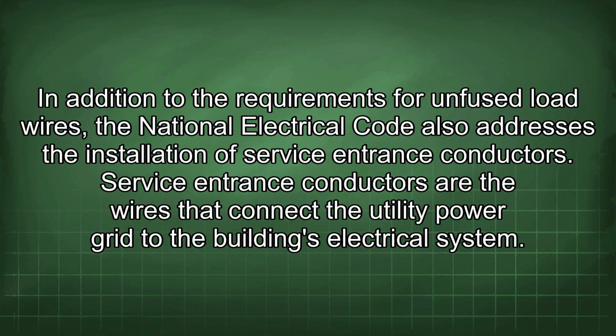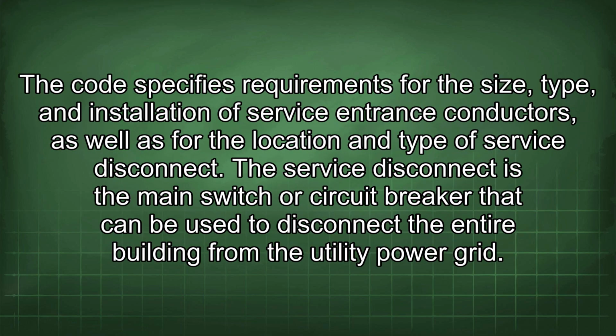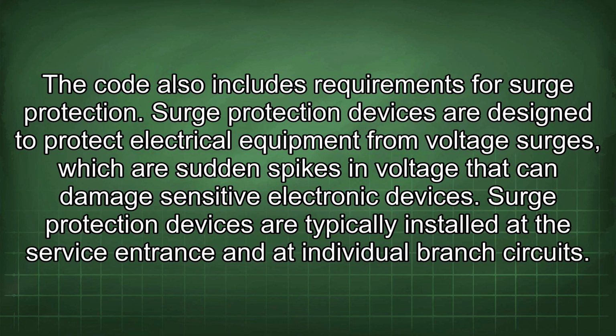In addition to the requirements for unfused load wires, the National Electrical Code also addresses the installation of service entrance conductors. Service entrance conductors are the wires that connect the utility power grid to the building's electrical system. The code specifies requirements for the size, type, and installation of service entrance conductors, as well as for the location and type of service disconnect. The service disconnect is the main switch or circuit breaker that can be used to disconnect the entire building from the utility power grid. The code also includes requirements for surge protection.